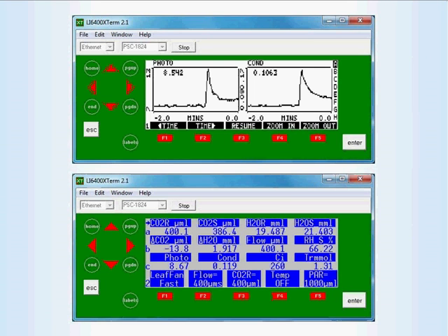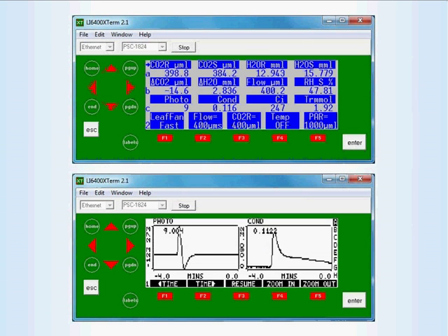After allowing the leaf to acclimate for a further 15 minutes or so, the gas analyzers were again matched, and then the desiccant knob was put to the middle, so that just about 50% or maybe a little bit less of the air was scrubbed and the remainder bypassed the desiccant.